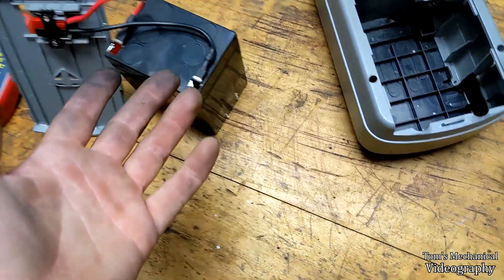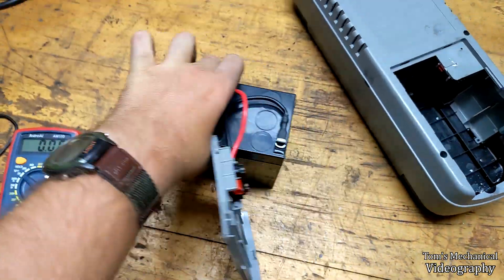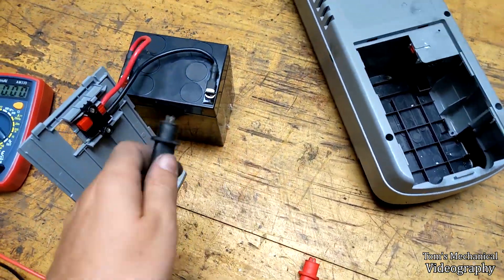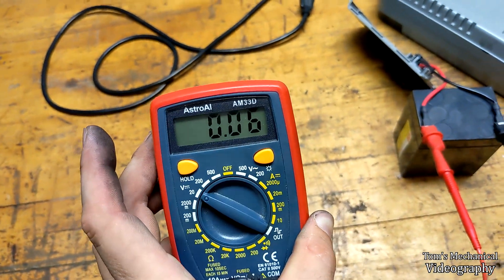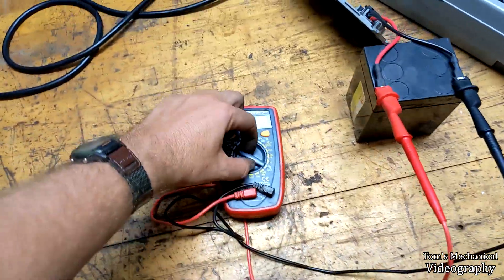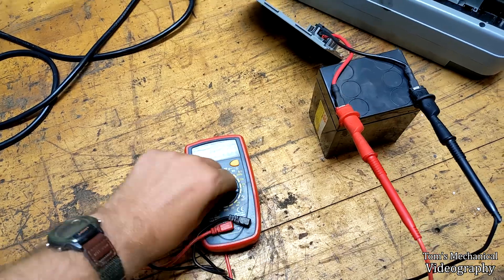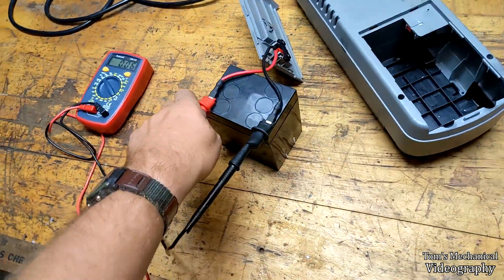From this one, there's a fairly good indication the battery has failed because there's a bunch of white smuts on it and it seems to be a little bit bulged. I've got the voltmeter set to 20 volts DC and we're just going to hook this up to the contacts and see what kind of voltage this thing is putting out. According to my voltmeter, it is putting out six one-hundredths of a volt — it should be something like 12.5. So that's not a great sign. 60 millivolts is not good, and those are hooked directly to the battery contacts.